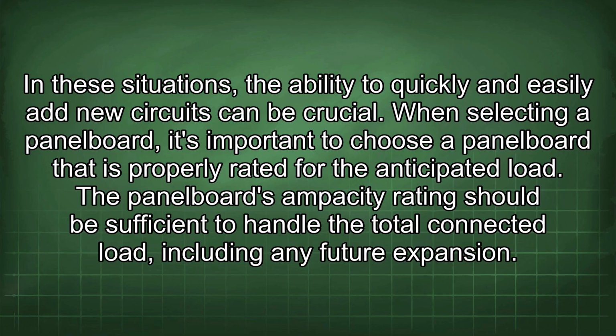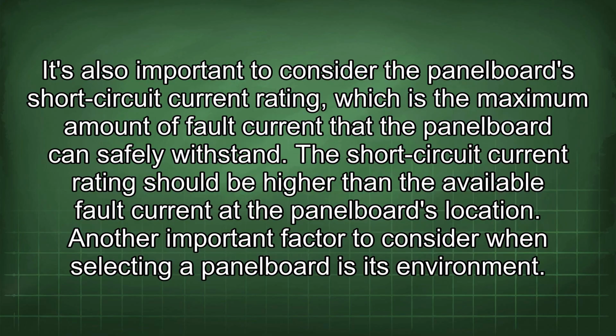When selecting a panel board, it's important to choose a panel board that is properly rated for the anticipated load. The panel board's ampacity rating should be sufficient to handle the total connected load, including any future expansion. It's also important to consider the panel board's short circuit current rating, which is the maximum amount of fault current that the panel board can safely withstand. The short circuit current rating should be higher than the available fault current at the panel board's location.